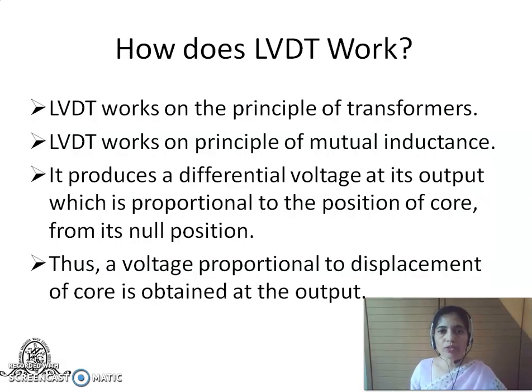The LVDT works on the principle of transformers, that is, the principle of mutual inductance. It is going to produce a differential voltage at the output. This differential voltage will be proportional to the displacement of the movable core. How far it is from the null position will decide the voltage which is induced in the two secondaries, and therefore the differential voltage. So the output voltage is proportional to the displacement of the core.